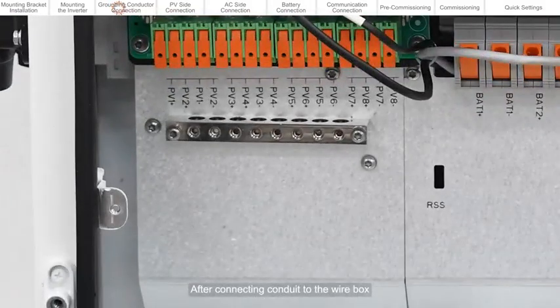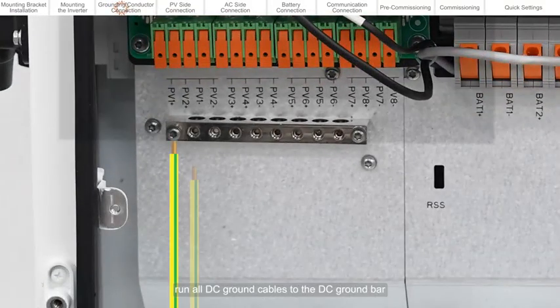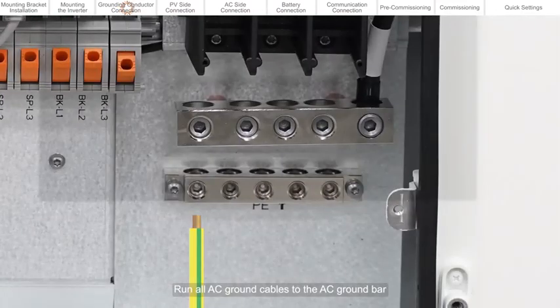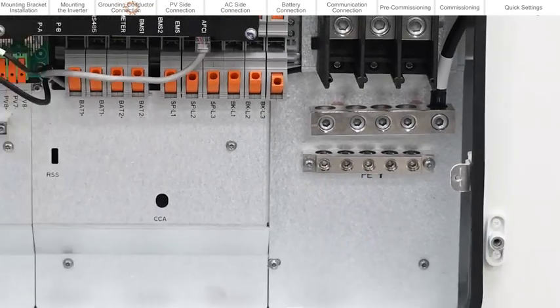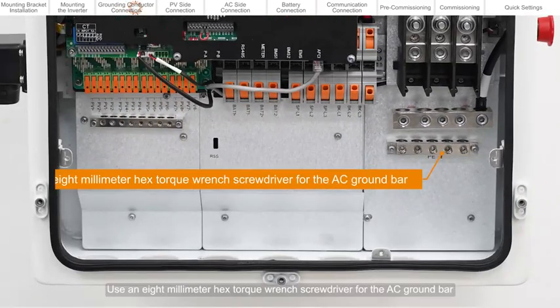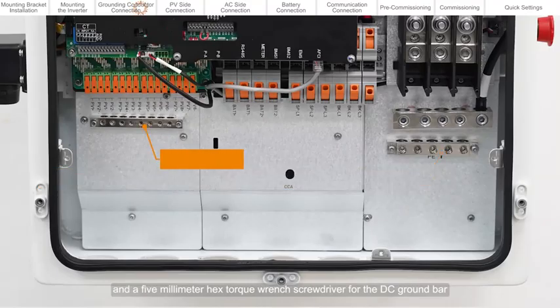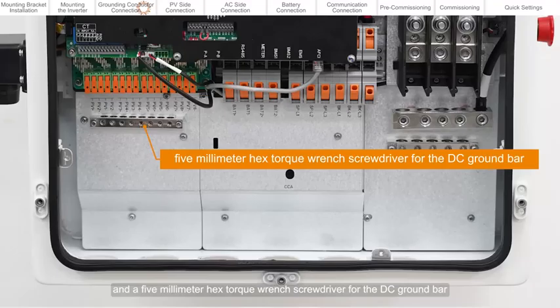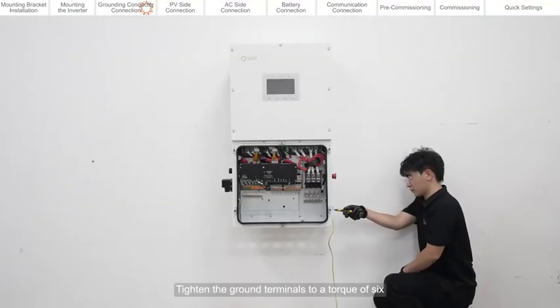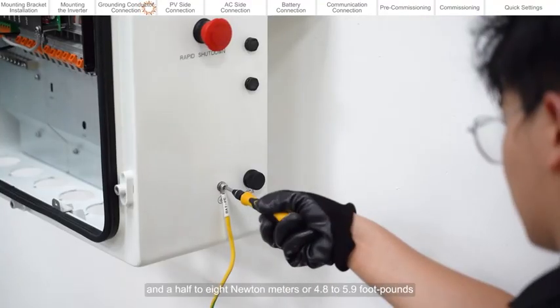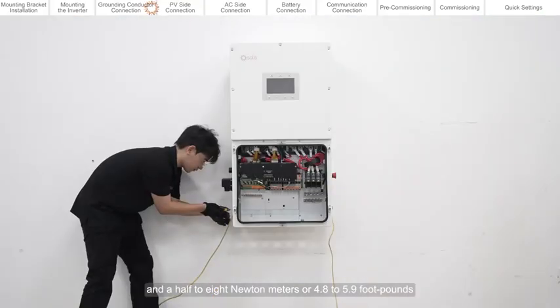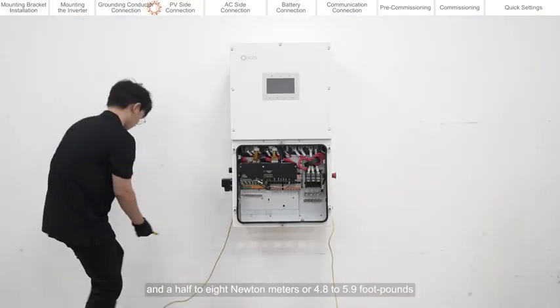After connecting conduit to the wire box, run all DC ground cables to the DC ground bar. Run all AC ground cables to the AC ground bar. Use an 8mm hex torque wrench screwdriver for the AC ground bar and a 5mm hex torque wrench screwdriver for the DC ground bar. Tighten the ground terminals to a torque of 6.5 to 8 Newton meters, or 4.8 to 5.9 foot-pounds.